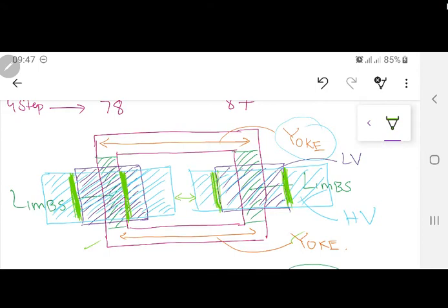It's a three-phase transformer, so you have to take into consideration that you are going to have partial discharge between these two, because you are keeping them close. The second concept is that this distance should be an adequate value so that oil can still flow and cool down the winding. So this is the first design procedure.